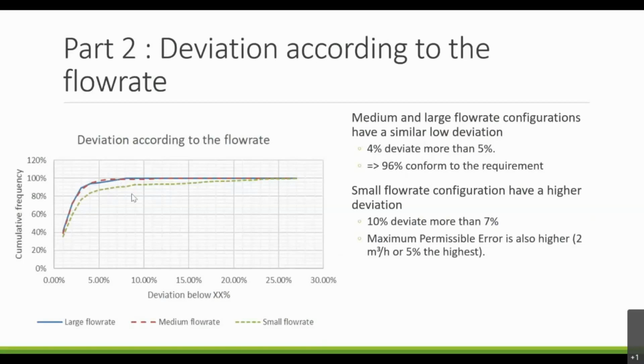We see that small configurations also have a higher deviation, with 10% that deviate by more than 7%, but the maximum permissible error, at least in France, is also higher, because it's 2 cubic meters per hour or 5%, whichever is the highest, and for small flow rates, sometimes 2 cubic meters per hour is higher than 5%.